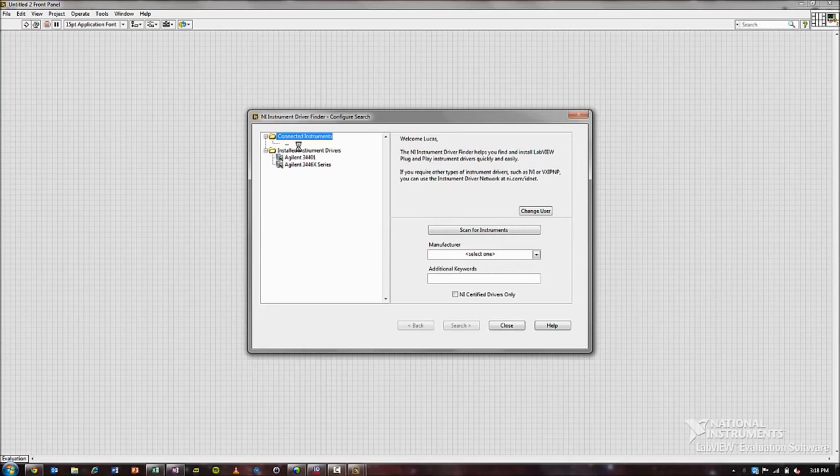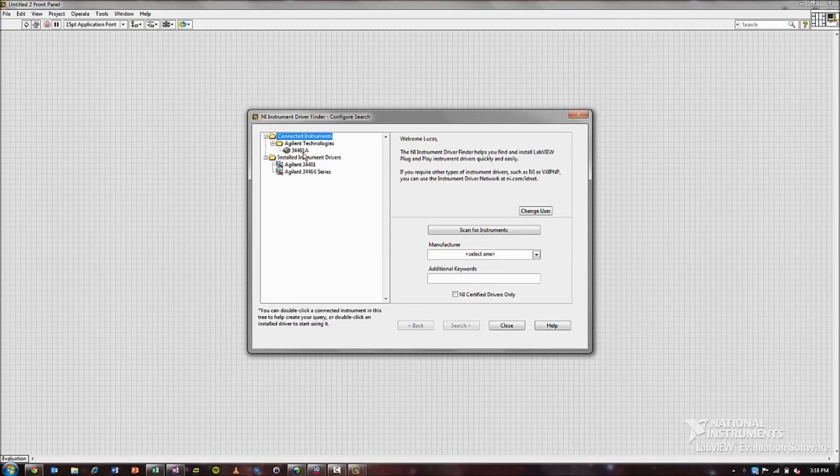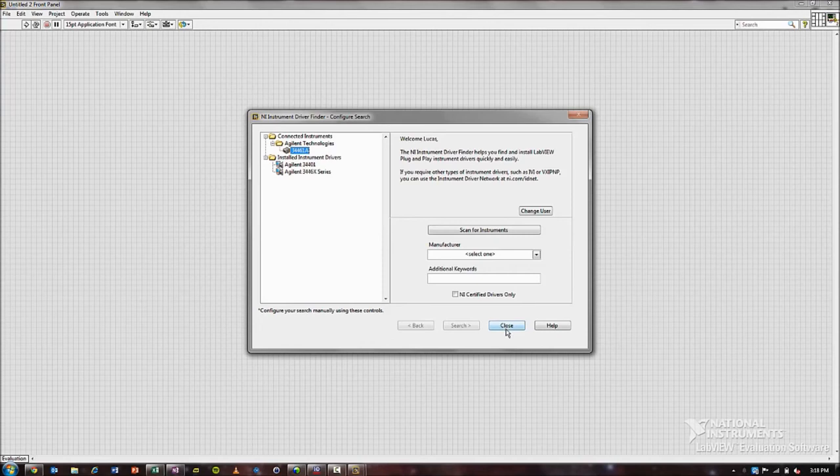this little tree diagram will show you whether or not LabVIEW can see your instrument and then you can import it into LabVIEW and control the front panel with different LabVIEW commands. And there it is. The Agilent 34461A that we connected just a few minutes ago has shown up in LabVIEW.